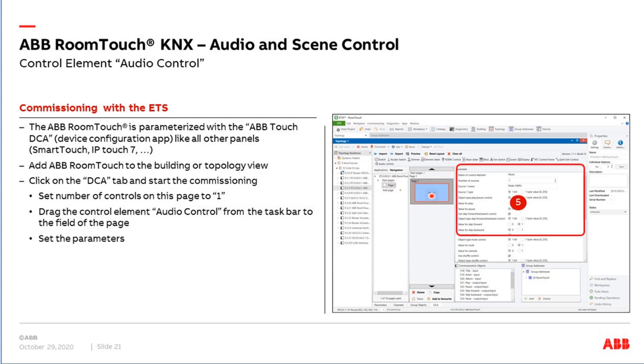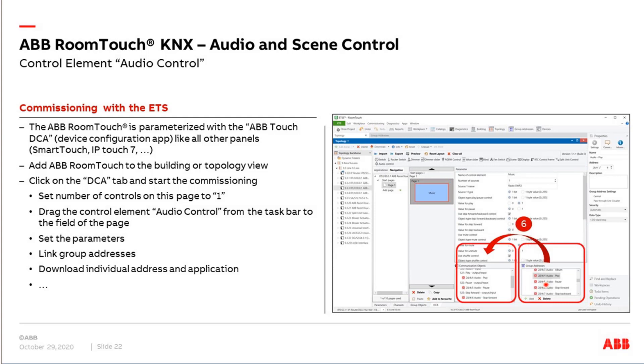Via drag and drop we take the Audio control from our taskbar and add it to the page. The next step is to click on the page — it turns orange — and then set all the parameters on the right side: how many sources or playlists we want to control, whether to use shuffle mode, and so on. Then we link the group addresses inside the DCA app by clicking on the RoomTouch device to get all group objects of this audio control element, dragging and dropping group addresses from the right side. Finally, download the individual address and application.